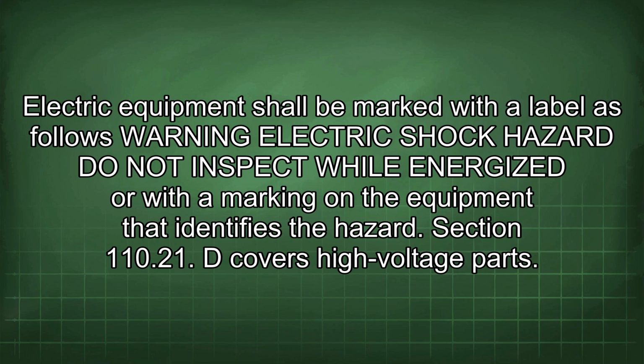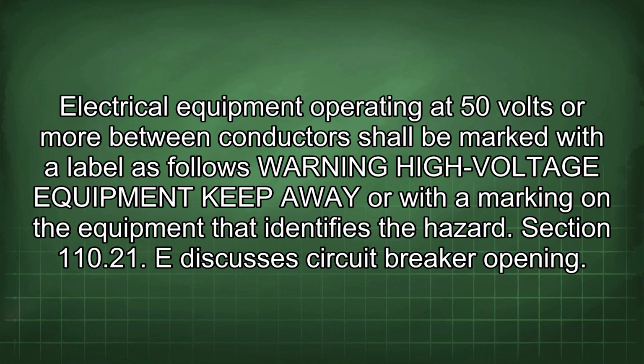Section 110.21(D) covers high voltage parts. Electrical equipment operating at 50 volts or more between conductors shall be marked with a label as follows: "Warning, high voltage equipment, keep away," or with a marking on the equipment that identifies the hazard.